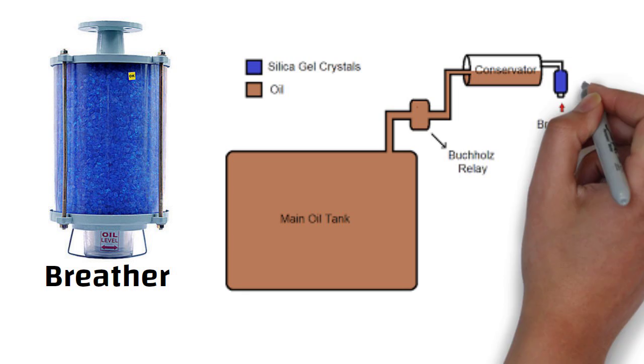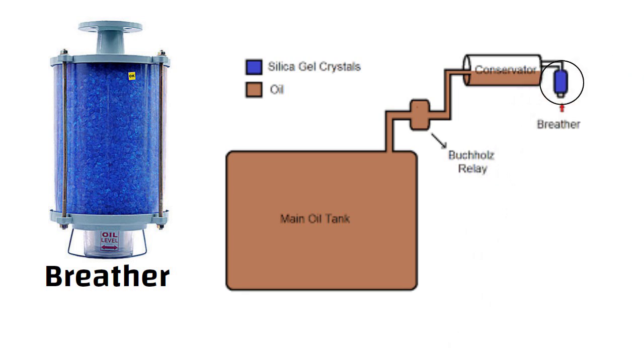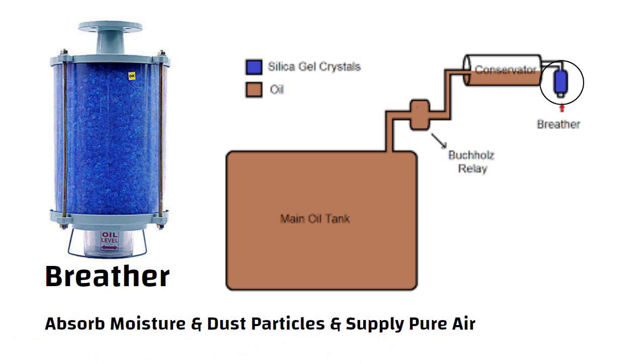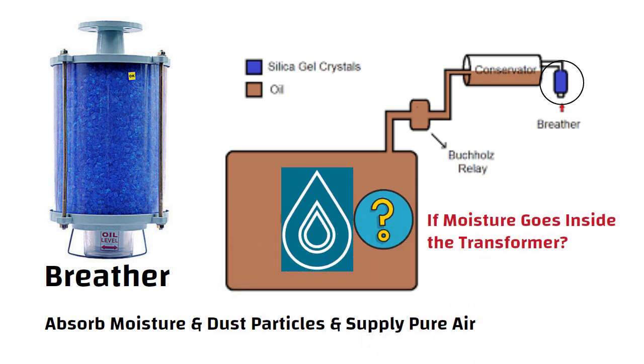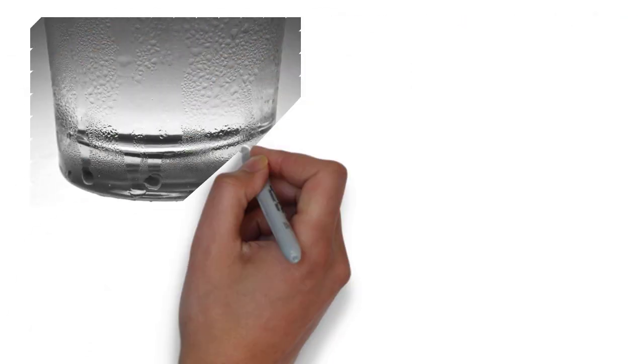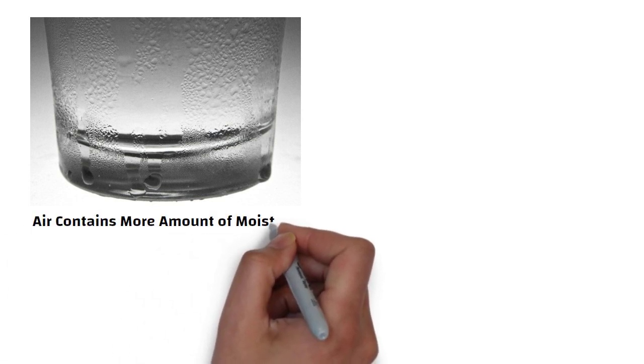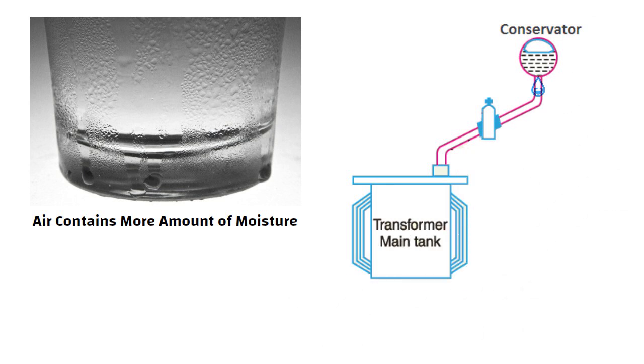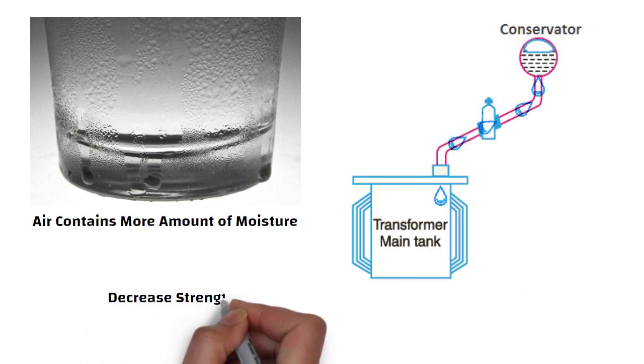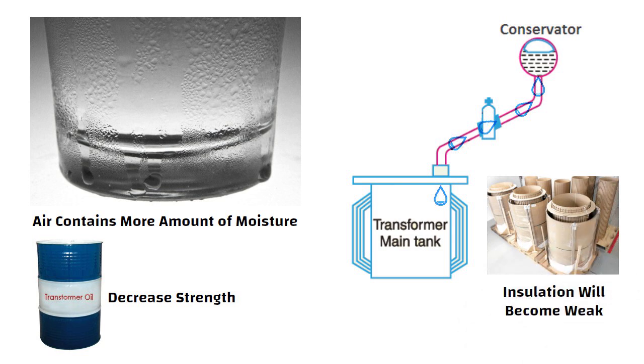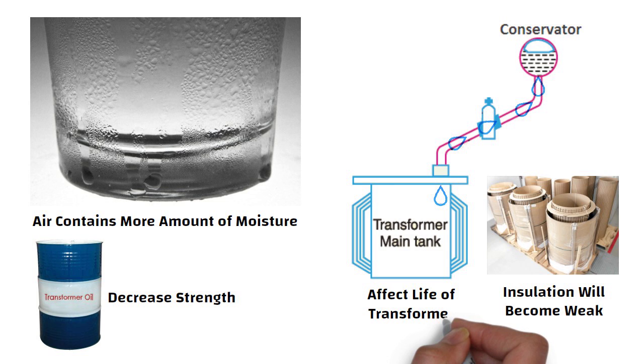Now let us understand the breather. You can see in this picture, the breather is attached to the conservator tank. The main function of the breather is to absorb moisture and dust particles and supply pure air inside the conservator tank. Now here the question is, if moisture goes inside the transformer, then what will happen? Normally the air contains moisture, especially in humid areas, where the air contains more moisture. If this moisture goes inside the transformer, then it will decrease the strength of the oil, the insulation will become weak, and ultimately it will affect the life of the transformer.